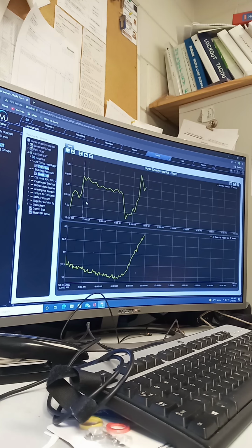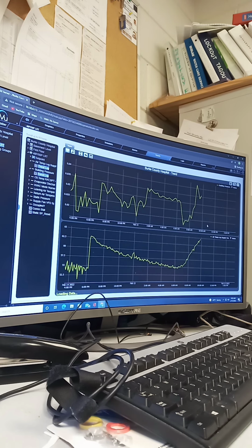So this is how we can go in and start troubleshooting something. What was the unit doing over this period of time? Was it in cooling? Was it in heating? What did the discharge air do when we told it to change its set point? All that kind of stuff. So now I can run trends on this and look at it over a period of time. Okay. And this server is a pro server, so you can run as many trends as you want.